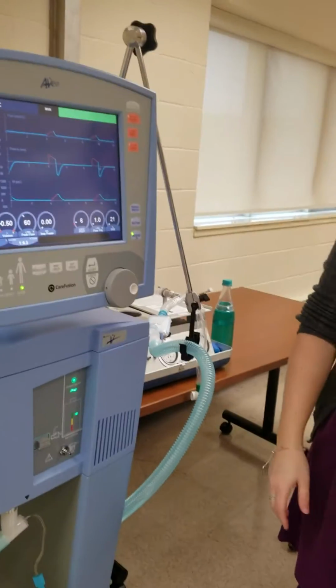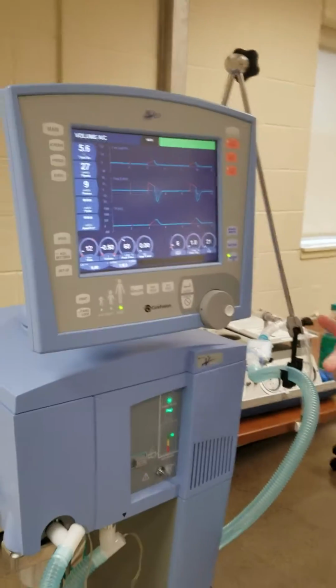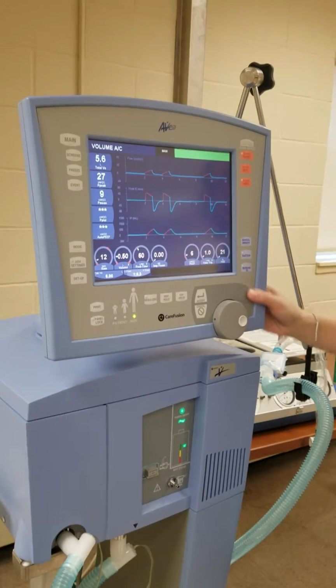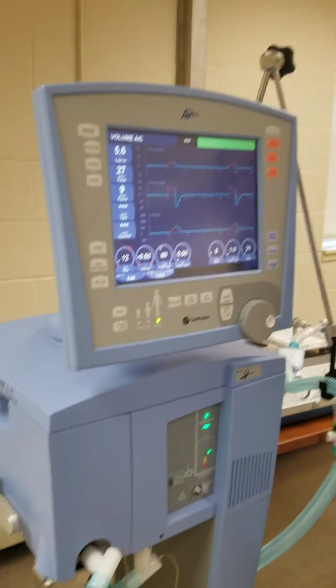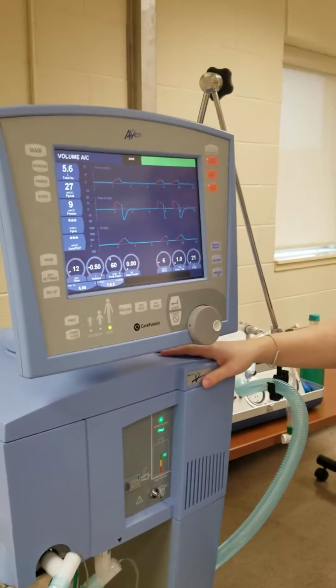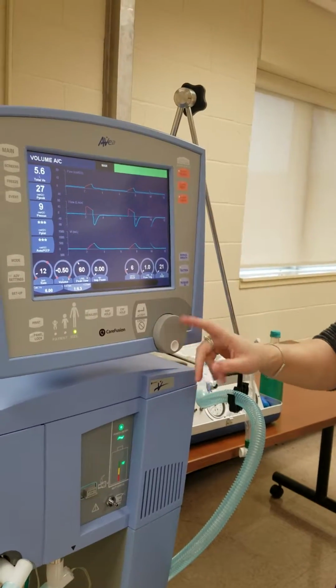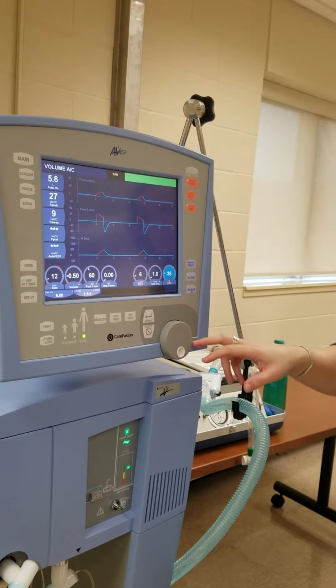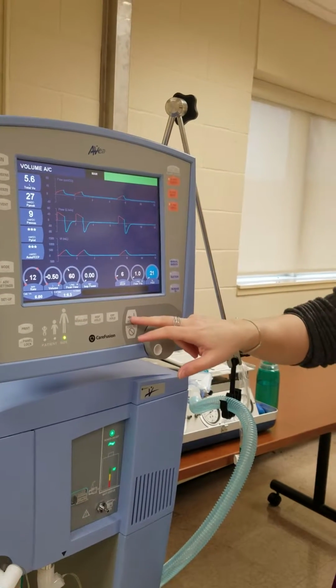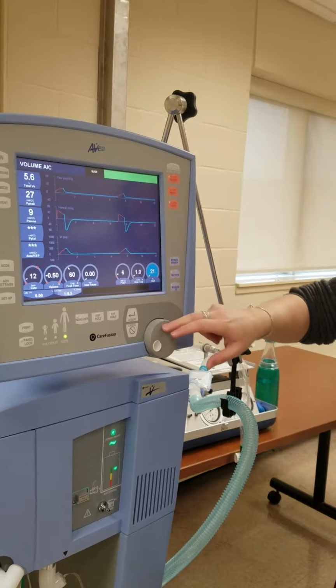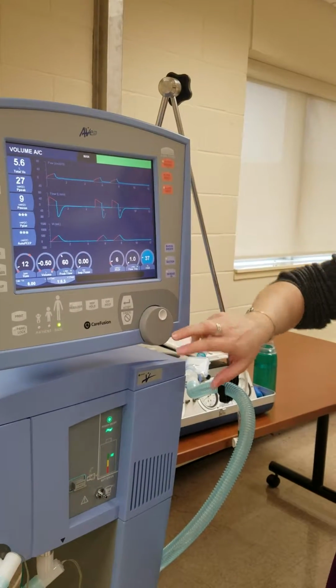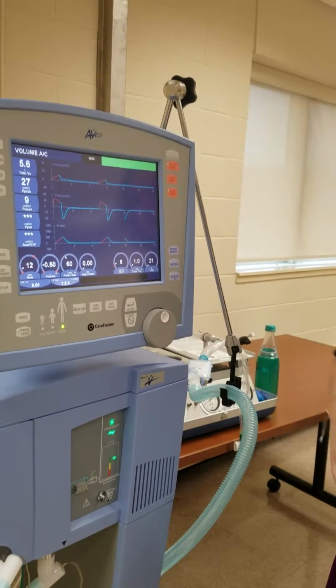Will you see it here if it? Nope. No. Okay. As long as that light is on, I know I'm on 100% FiO2. Okay. Well, after that 2 minutes is over and that light goes off, I'm no longer on 100% FiO2. Or you can click it off before that 2 minutes is up. Gotcha. You've seen we use this to dial numbers in. So if you want to crank that up, crank it down, accept or cancel. So let's say I went up to 30 and then I go, oh wait, I didn't want to do that. I click cancel and there's right there.